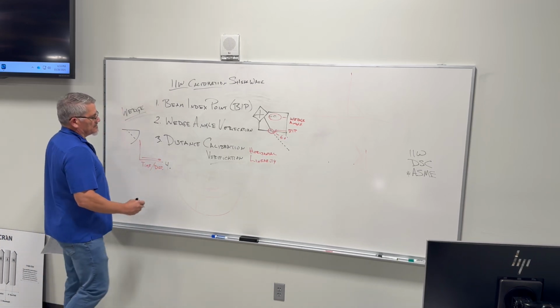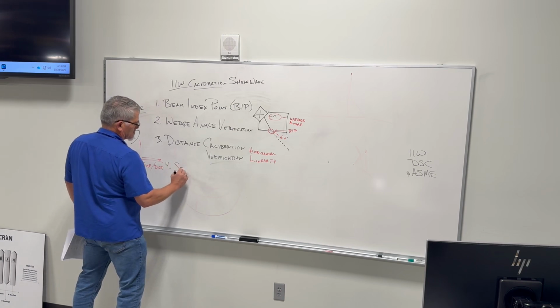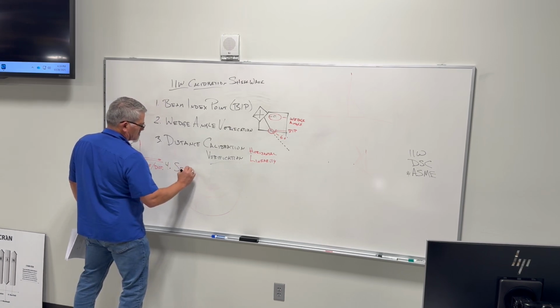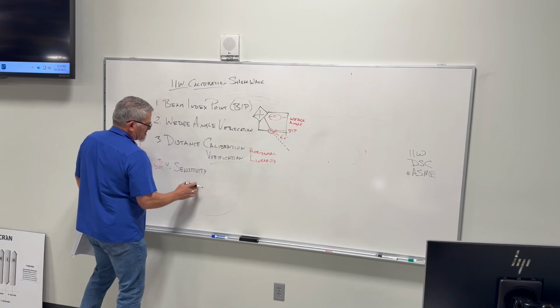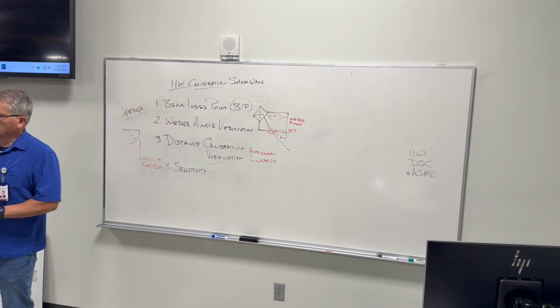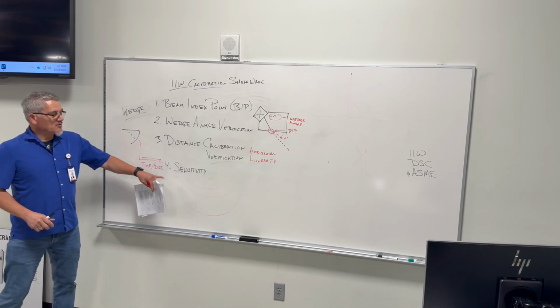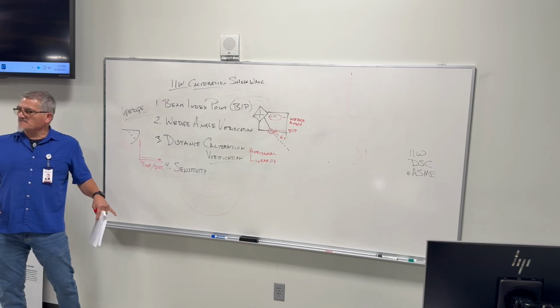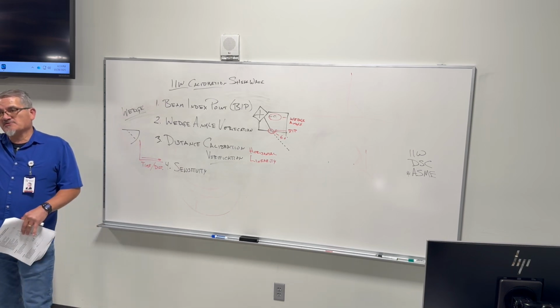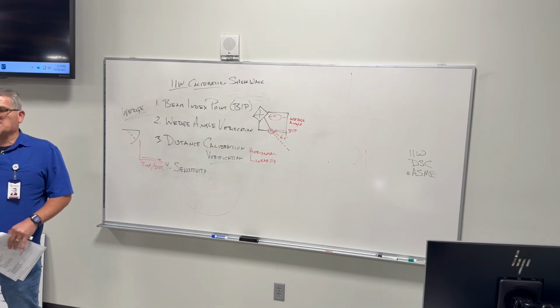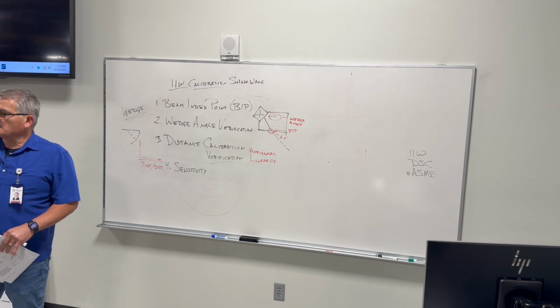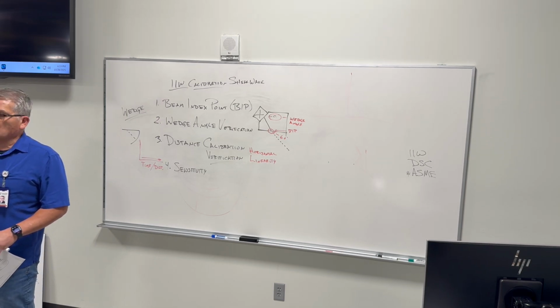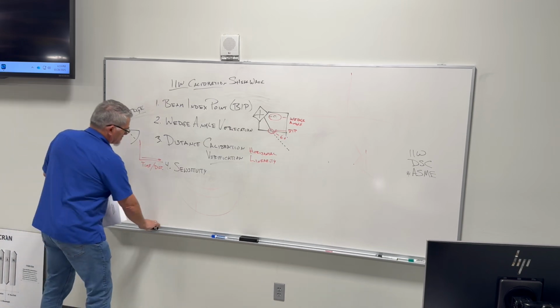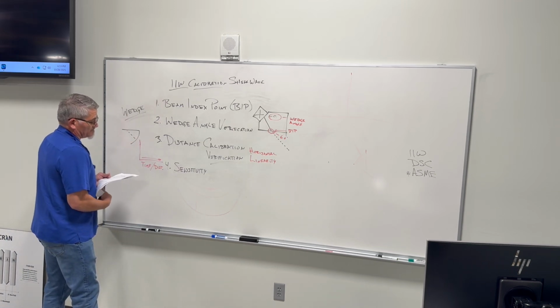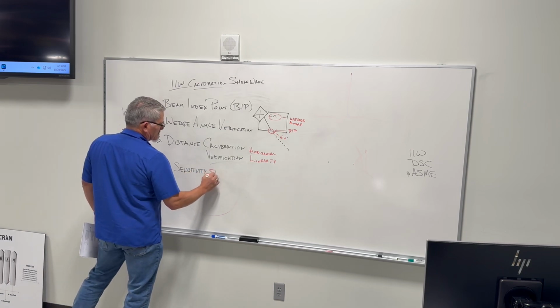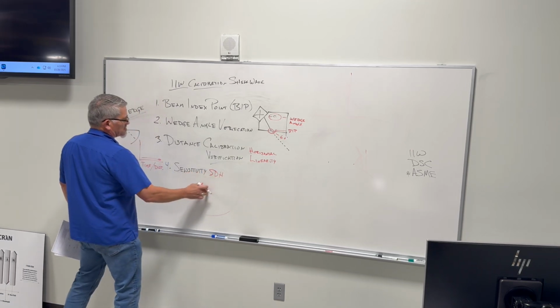The last step that we're going to do is perform a sensitivity check. Basically, this becomes more of our standardization, if you will. We're standardizing. Because as you recall, on the flat bottom hole standards, we put that transducer on the top of that standard, and we're looking for that small flat bottom hole, which becomes our reference reflector. Okay, that becomes what we're looking for. Well, in the case of this instrument here, with this block, we're going to establish this on the side drill hole.